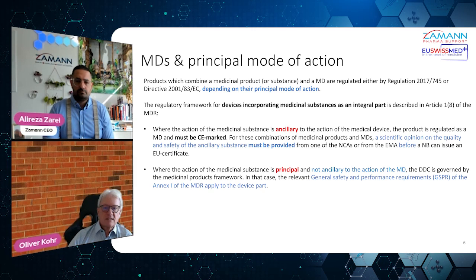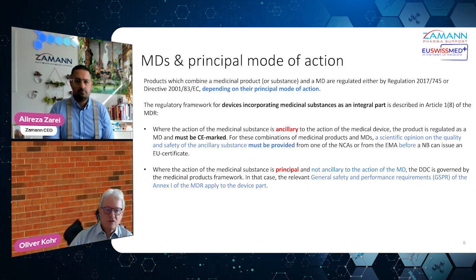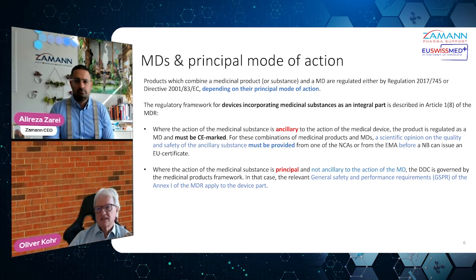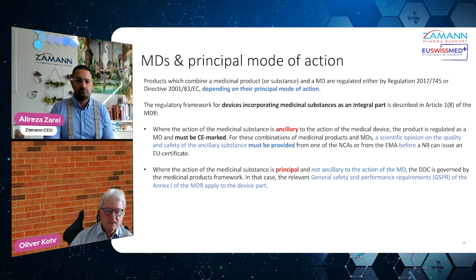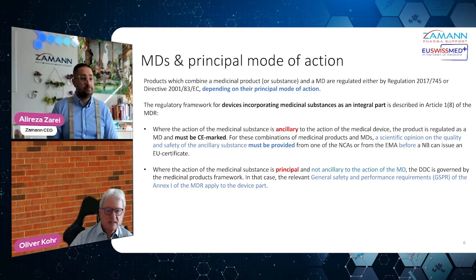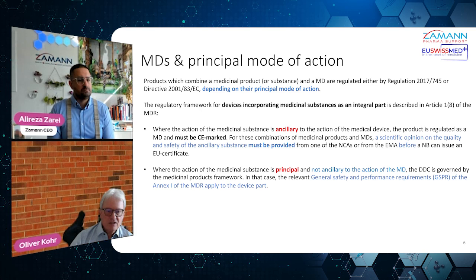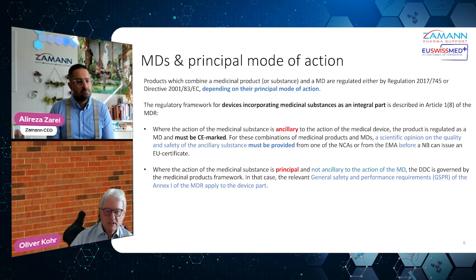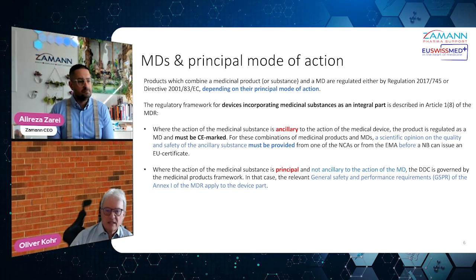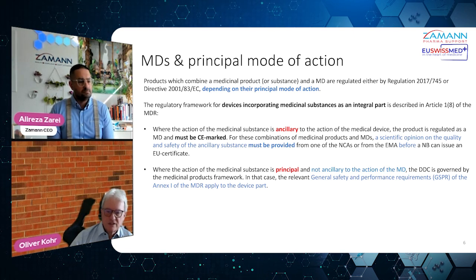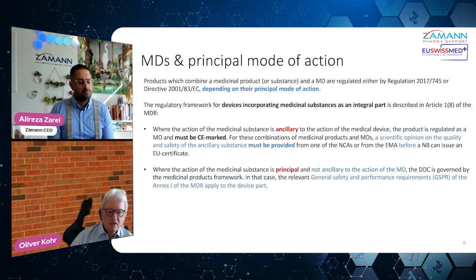Important thing is, as I mentioned before, the principal mode of action. This is the key thing you have to think about. What's the mode of action? Is it the medicinal product, or is it principally the device? So if the action of the medicinal product is principal and not necessarily the action of the medical device, then basically your DDC is governed by the medicinal framework, right?